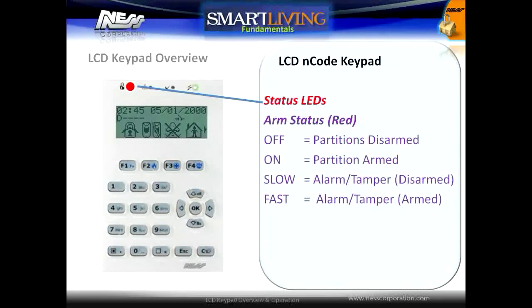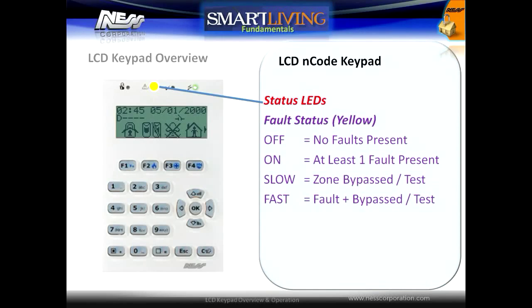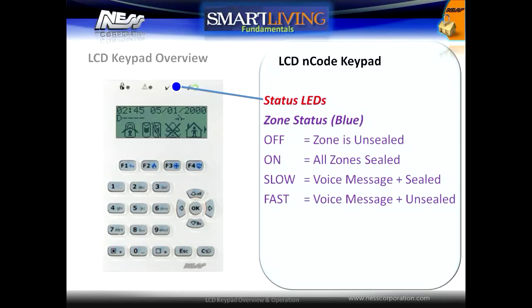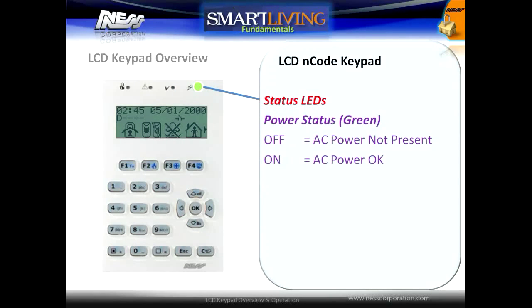The red arm status LED indicates arm status in any partition and also indicates system alarm. The fault status LED indicates if there are any system faults present or if there is a zone bypassed. The zone status LED indicates if all zones are sealed and if there is a voice message on a touchscreen keypad. The power status LED indicates that AC power is connected.